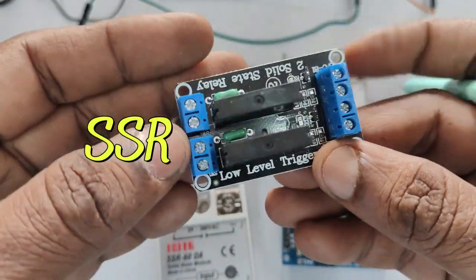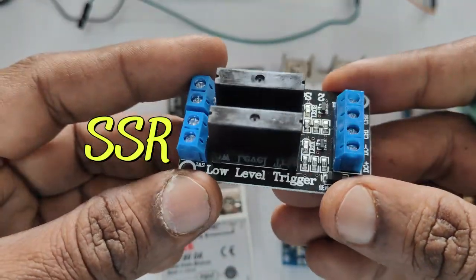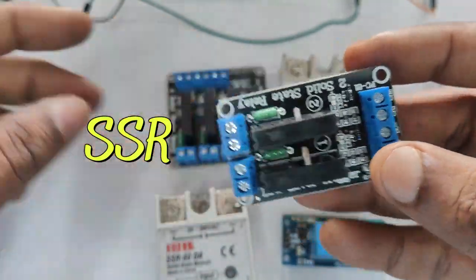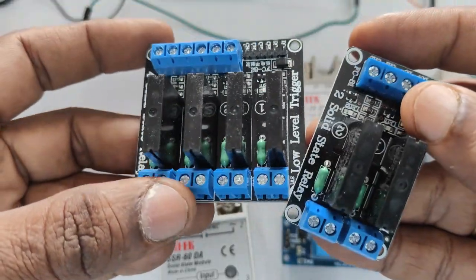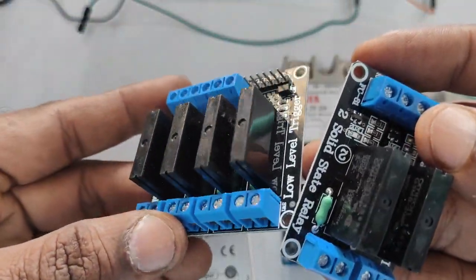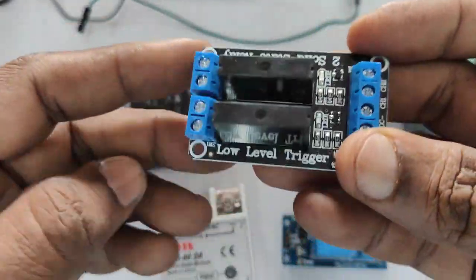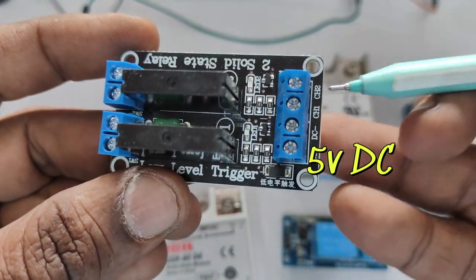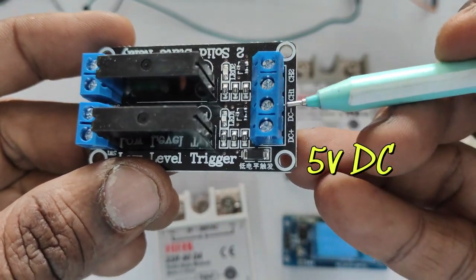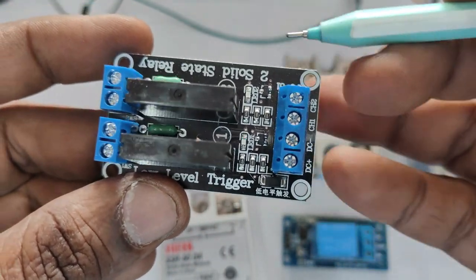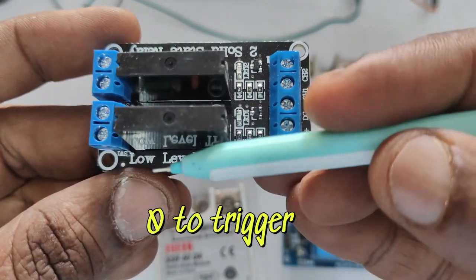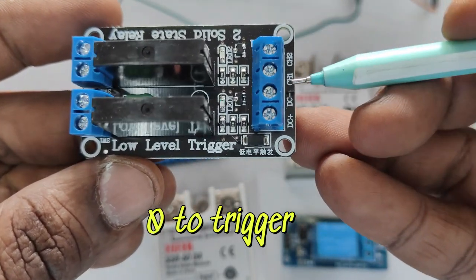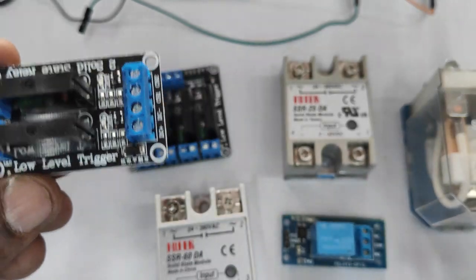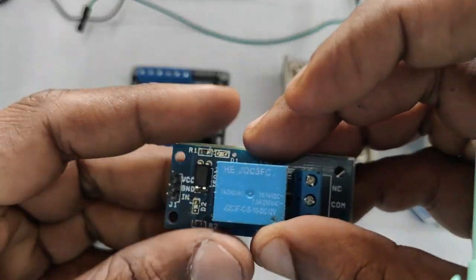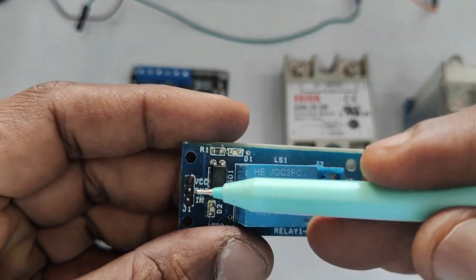But in SSR, there is no physical contact. This is a no contact relay, which enables high speed and high frequency operation. There are single channel, two channel, four channel, and eight channel relays. Instead of mechanical contacts, it has got electronic circuit. The advantage is that it switches on in microseconds, and 0 volt trigger is also available, and high voltage trigger is also available. You can apply 0 volt to trigger.